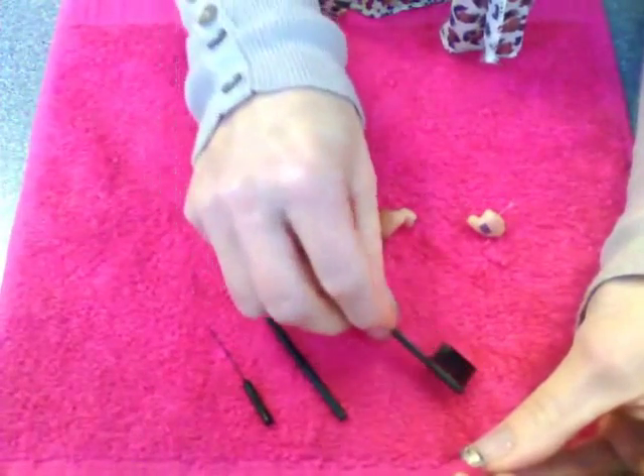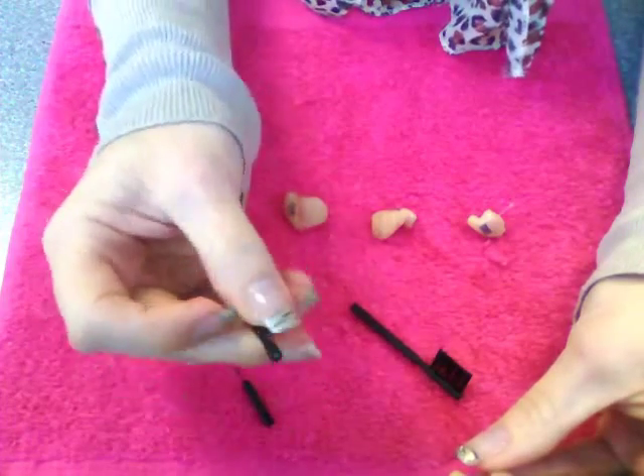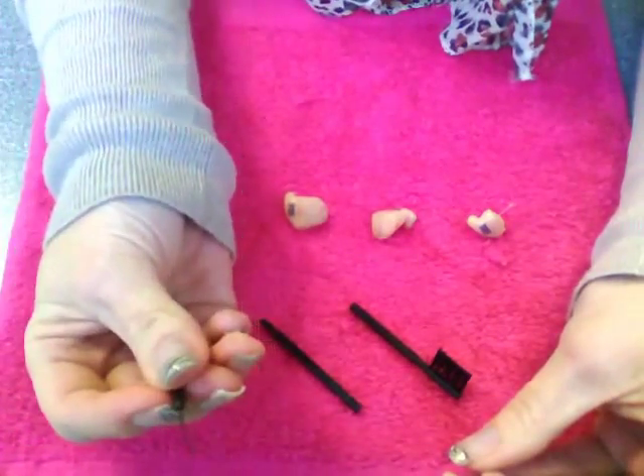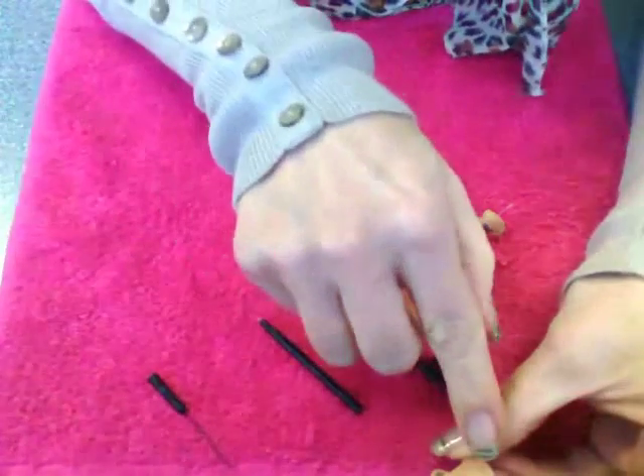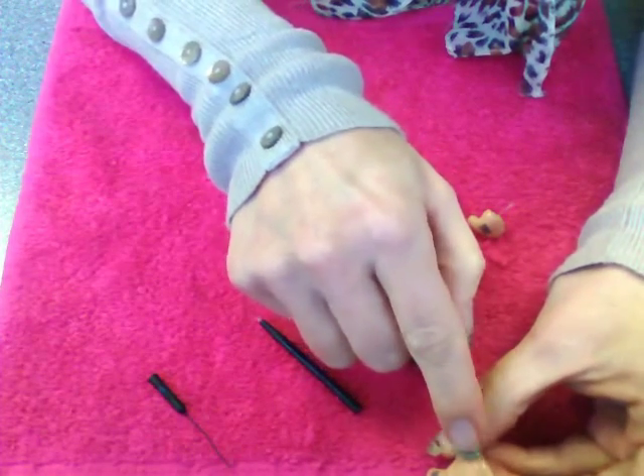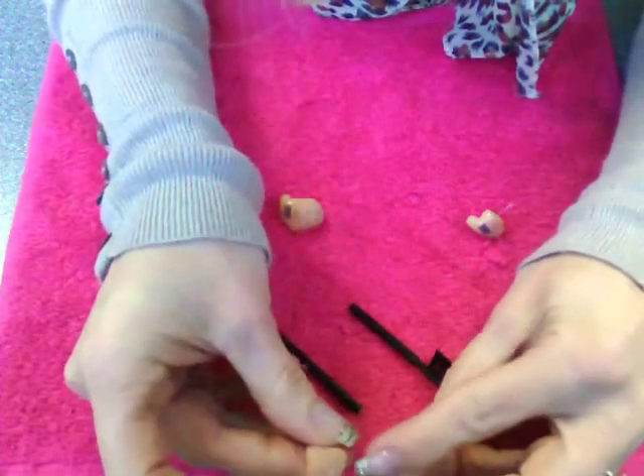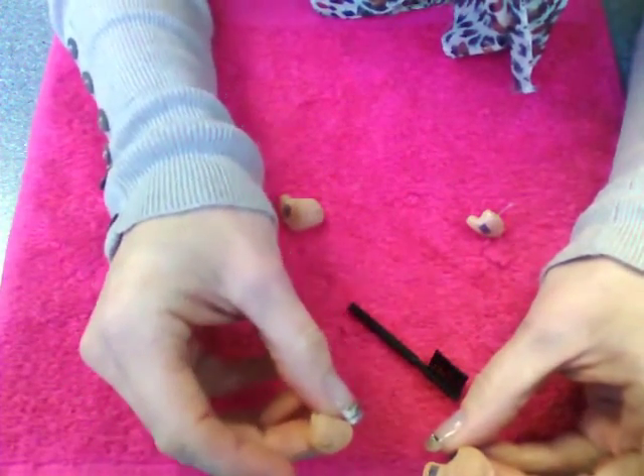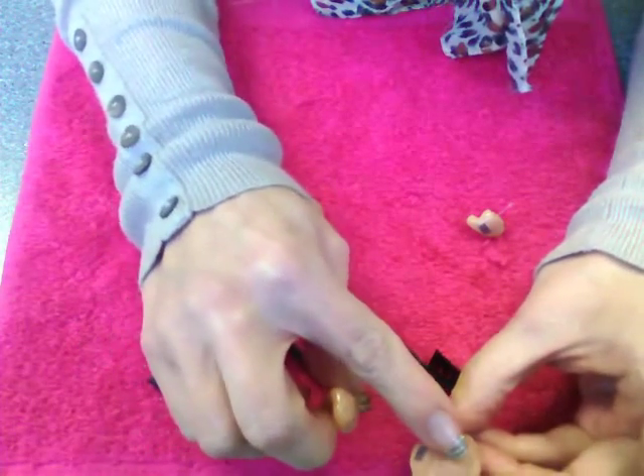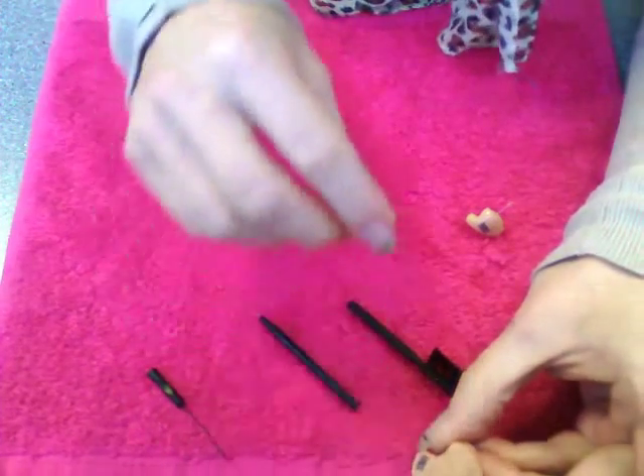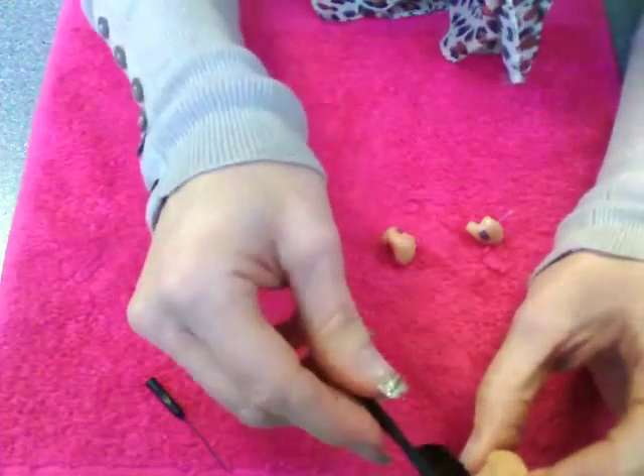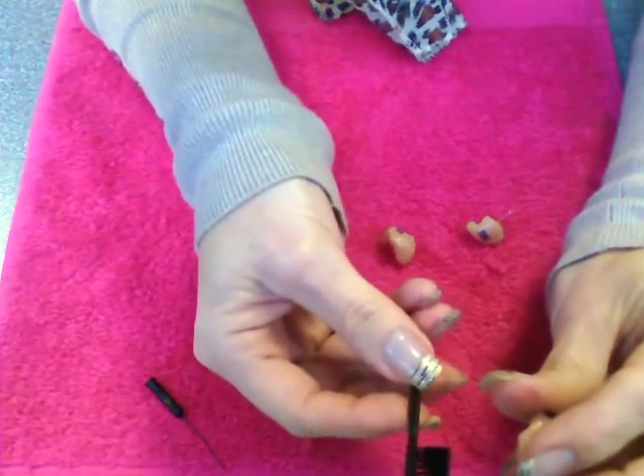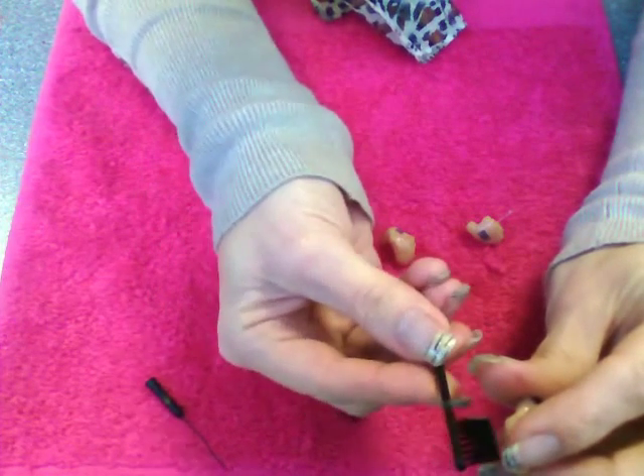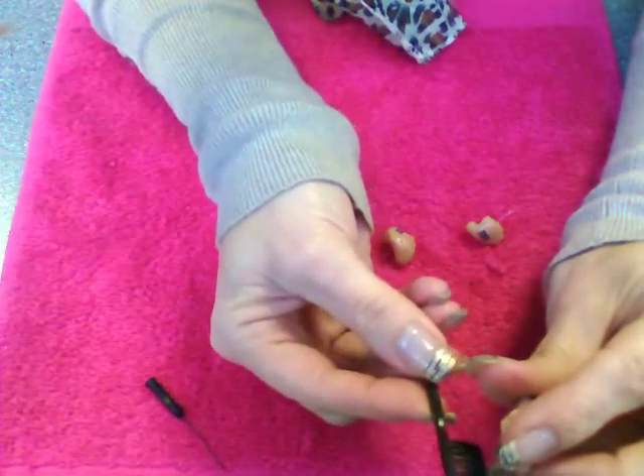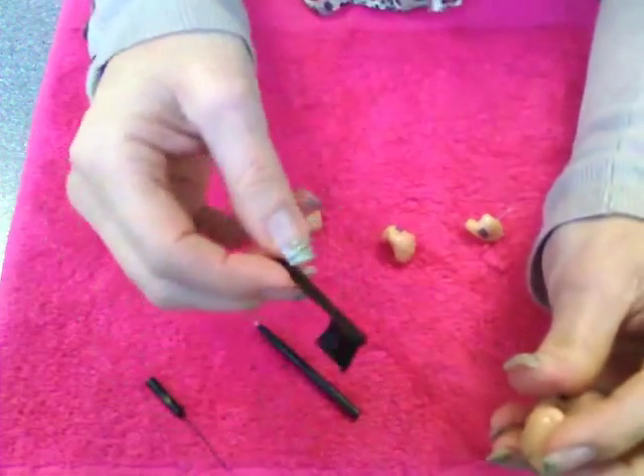Once you've wiped the aid all over, the sort of tools that you'll get in your kit normally are a brush, a pick, a magnet and a probe. So on your hearing aid, on the faceplate, you'll find that you've got a hole or two. These little holes, as you'll see on most of the hearing aids, are where your microphones are. Now if you've got any grease on your fingers, it can quite easily, on pushing the aid in, smother over the hole where the microphone is and prevent the aid from working. So very gently turn the aid slightly facing the floor and just gently brush over the microphone outlets so that anything covering them is likely to drop outwards rather than inwards. So that takes care of the microphones.